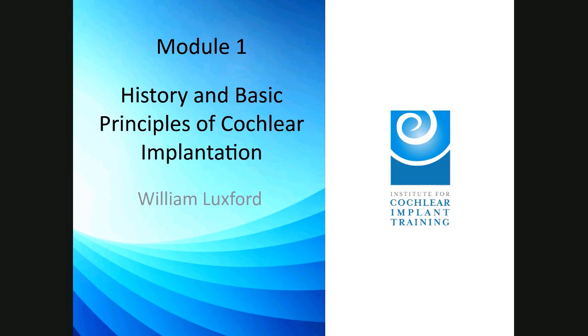And when you're using the electrodes, it provides stimulus. They try to have these 8, 12, or 22 electrodes and provide stimulus within the cochlea. Each company does it a little different way. At each moment, though, you're probably stimulating no more than maybe 4 electrodes across that array. So that cuts down on cross stimulation that might create an effect. If you make your stimulation too focused, you will have trouble with electrical, probably burnout of maybe some of the neural cells. Tom will be discussing that later in more of the electrical stimulation talk.